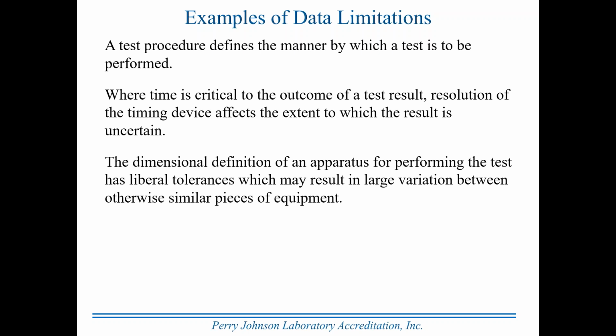The dimensional definition of an apparatus for performing the test has liberal tolerances, which may result in relatively large variation between otherwise similar pieces of equipment. Now, this might be an example like the two graphs we looked at that had equal standard deviations or measures of dispersion, but had different means. One machine might have one particular mean or amount of systematic variation because of the way it was assembled. Holes have a 32nd of an inch clearance for a bolt, or 0.75 millimeters clearance. And in one machine, it's shifted all the way to the left, and the next one, it's shifted all the way to the right. Both of them are acceptable and within specification for the equipment. But those are the kind of things that would produce systematic variation showing up as a bias in the readings.